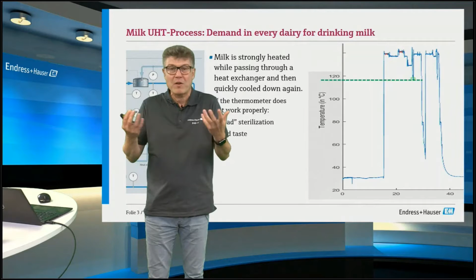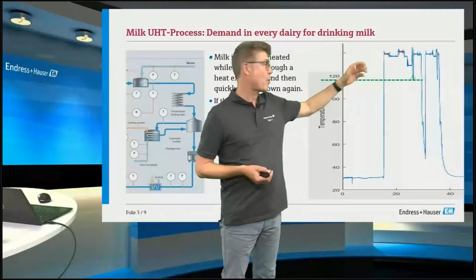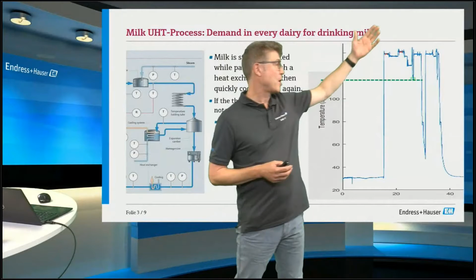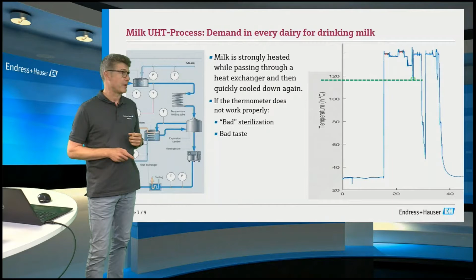And so it is very important to reach a certain temperature to kill the bacteria, but you cannot exceed this temperature, because if you heat the milk too much, you will taste that it was too hot. And so the temperature measuring points in the milk processes need to be calibrated quite regularly. In this example, a typical milk heater, it's heated up for a while, for some minutes or hours. The milk will continuously process, and sometimes it shuts down because you need to clean it. So this is one of the typical processes in the milk industry, in the food and beverage industry.